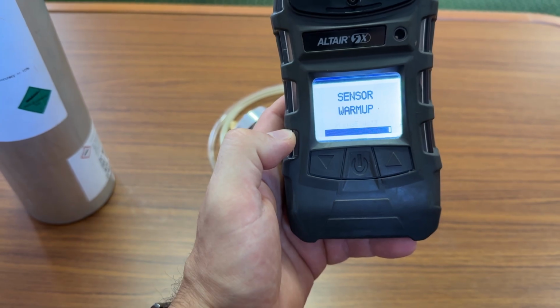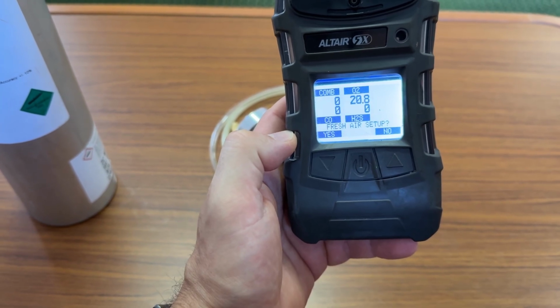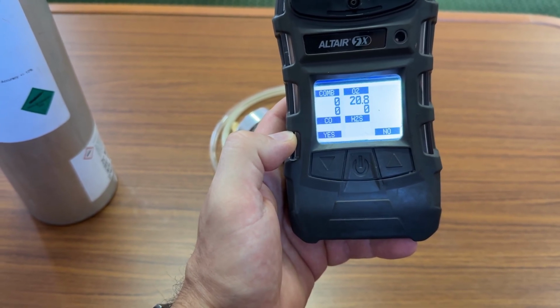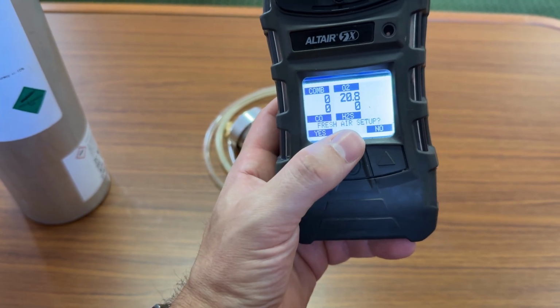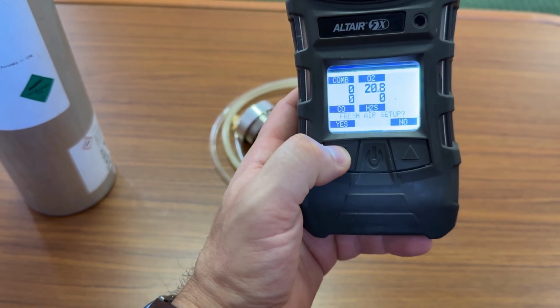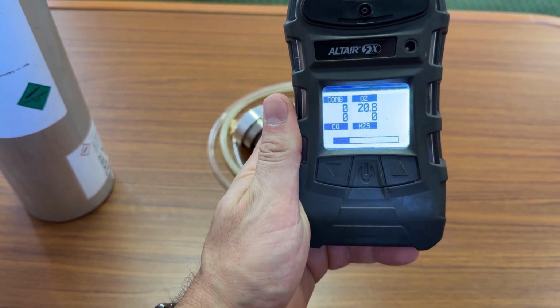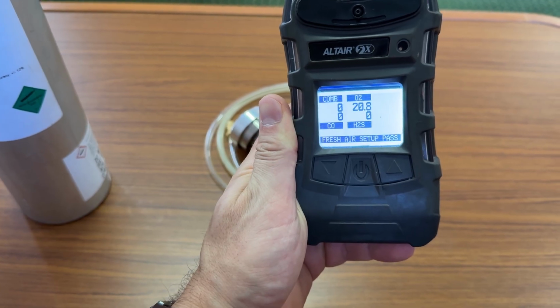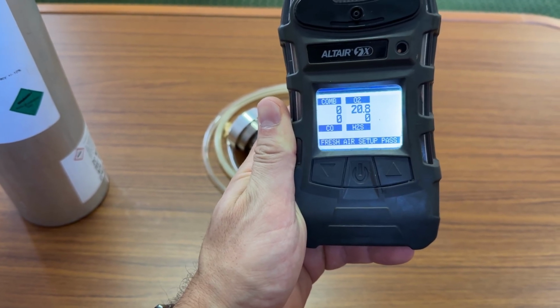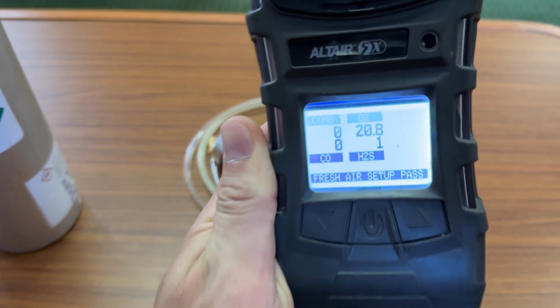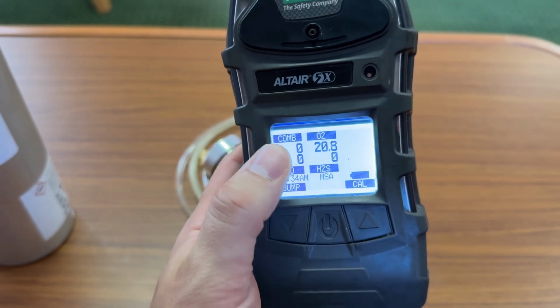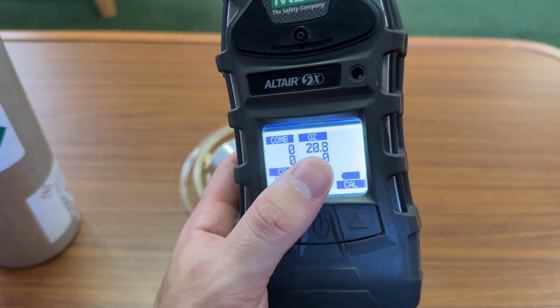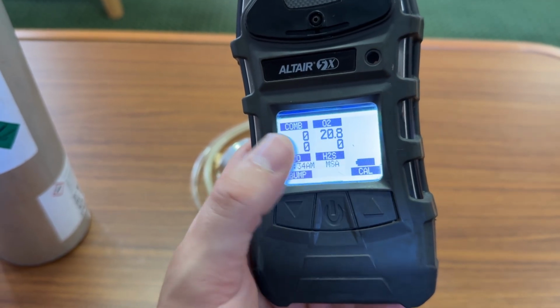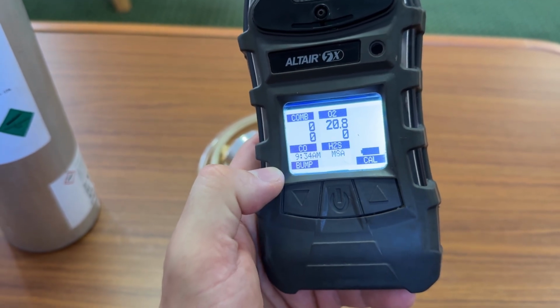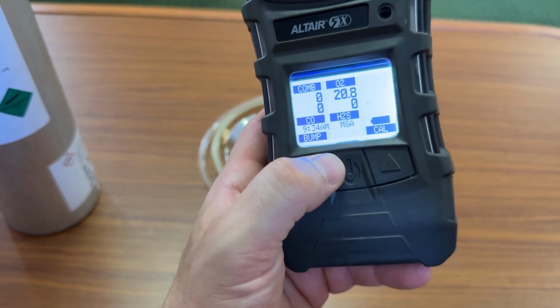Checking the sensors. There are 3 sensors inside here. Okay, fresh air setup. Press yes. Fresh air setup pass. So this is a normal concentration: 0 gases and oxygen 20.8. It's a normal concentration of the oxygen.